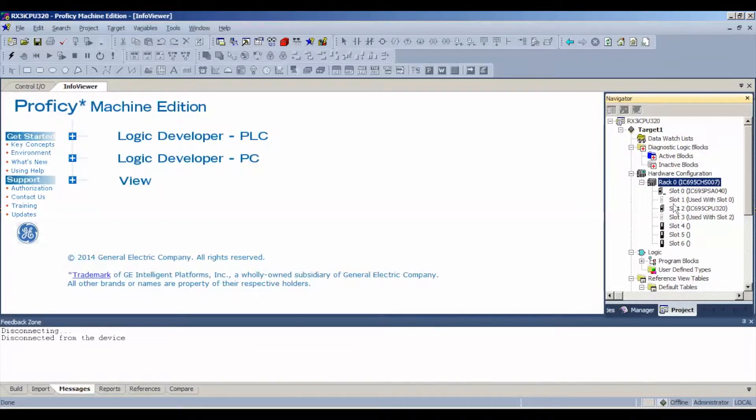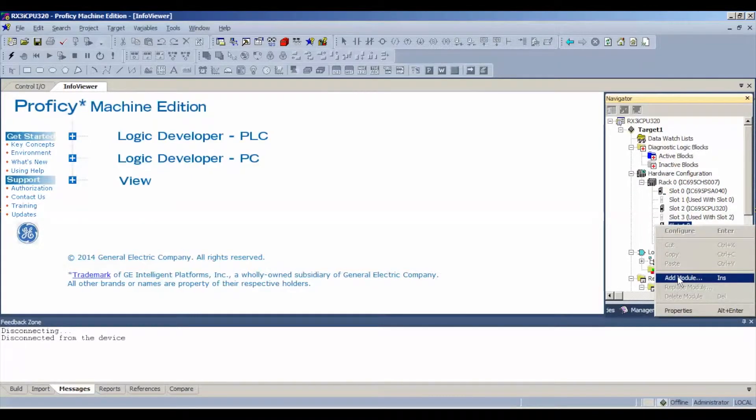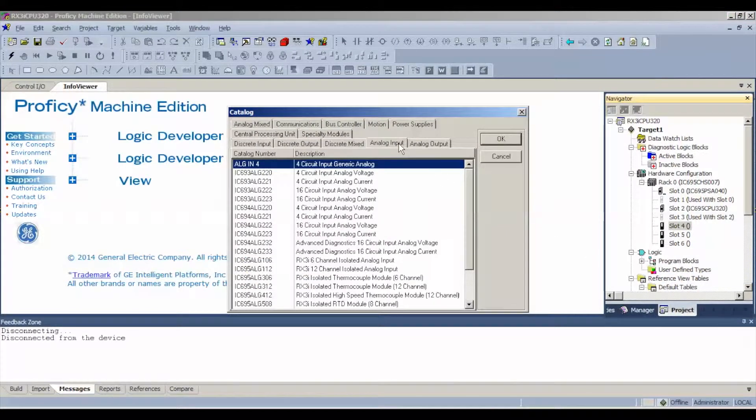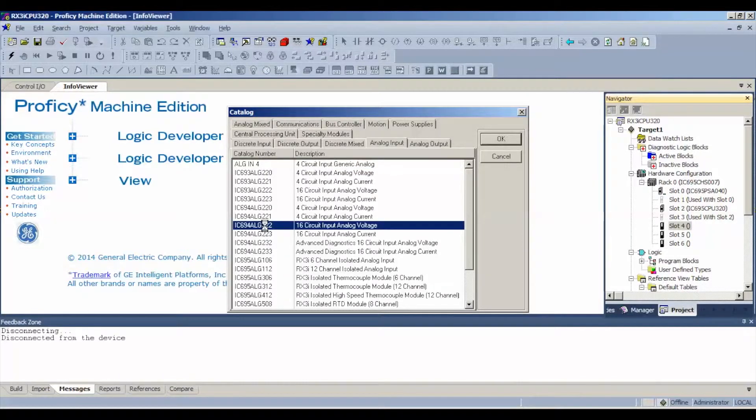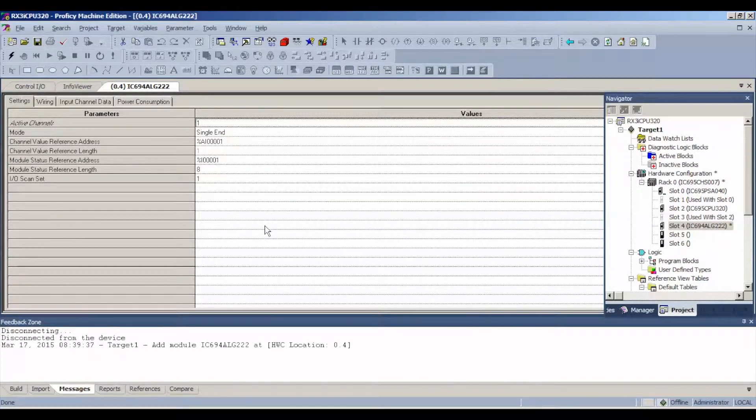My power supply is using two slots, slot 0 and slot 1, and my processor is using two slots as well, slot 2 and slot 3. That leaves me with the next available slot number 4. Now you can either double-click or right-click on slot 4, add module, analog input, and as we said before, it's an IC694ALG222.